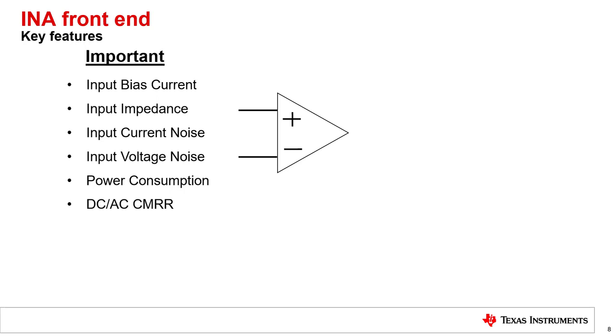In ECG systems, DC coupled systems need to attain high dynamic range. Power consumption is not always important as most hospital equipment runs off a wall supply, however as more and more ECG measurement systems are becoming mobile, consumer and even new hospital grade equipment is being designed for battery operation to allow patients and caregivers more mobility. Maintaining power within a few milliwatts is a great selling point. Finally CMRR is very important because a typical ECG system is exposed to a lot of common mode interference such as 50 to 60 Hertz power line noises.